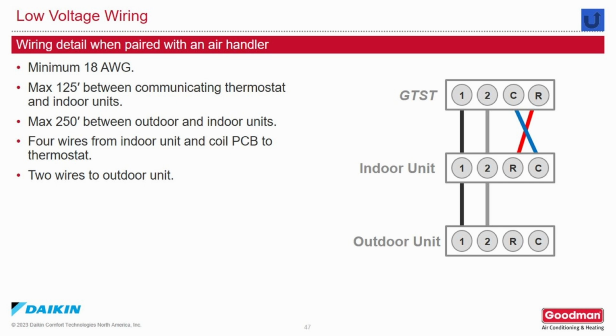The low voltage wiring detail when you're paired with an air handler: minimum of 18 gauge wire, but since this is for DC communication, beware of using too large a wire. 16 gauge maximum should be fine. Maximum wire distance between the communicating thermostats and the indoor units is 125 feet. Maximum distance between the indoor units and the outdoor units is 250 feet. 4 wires are required between the indoor unit and the coil PC board to the thermostat. 2 wires are required from the indoor unit to the outdoor unit.